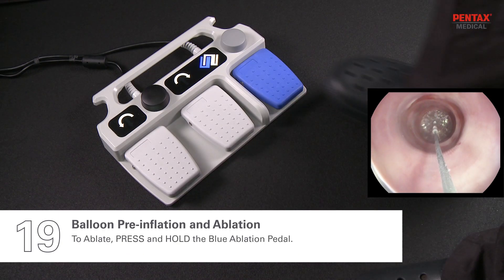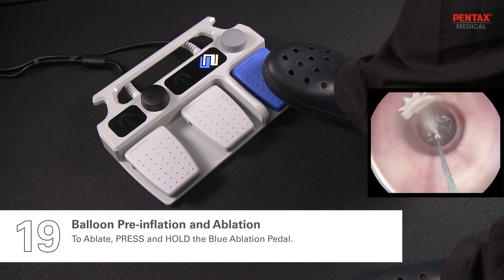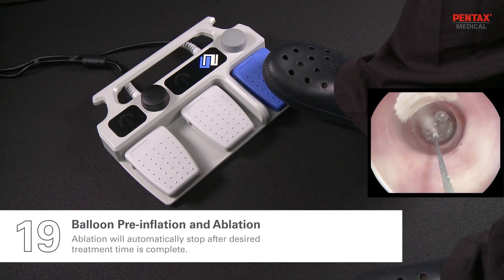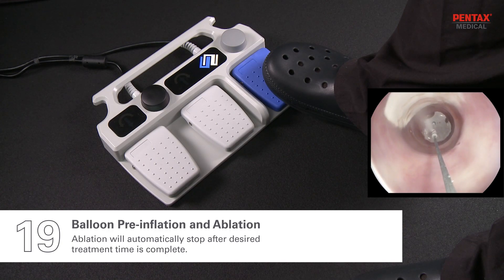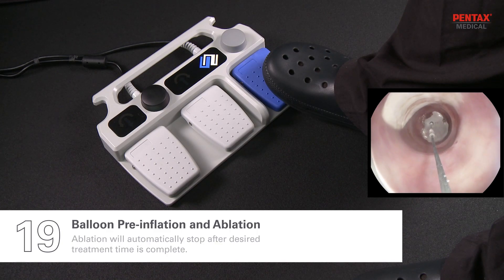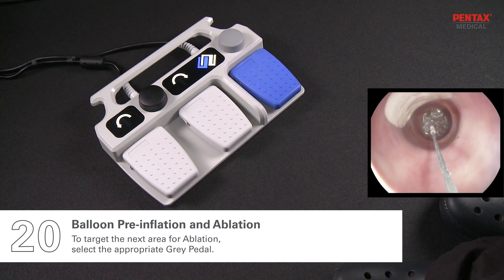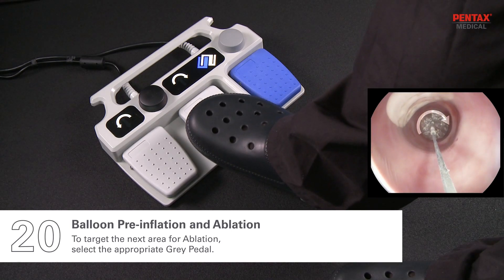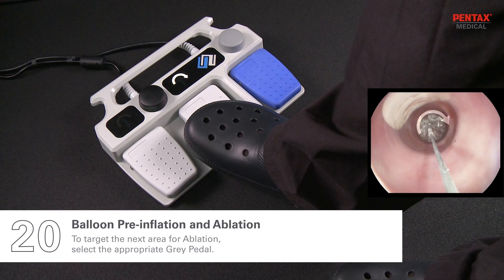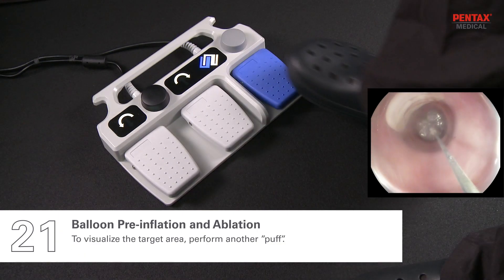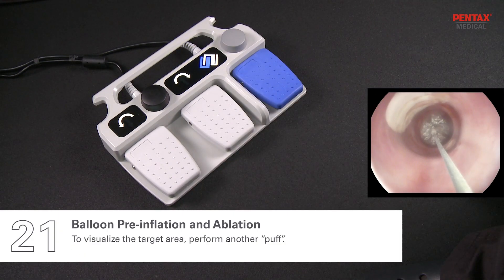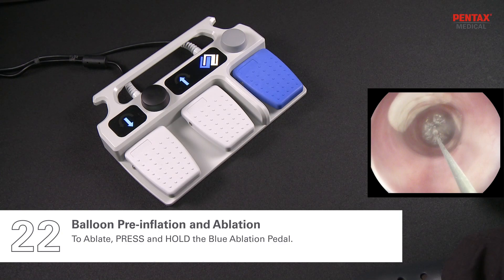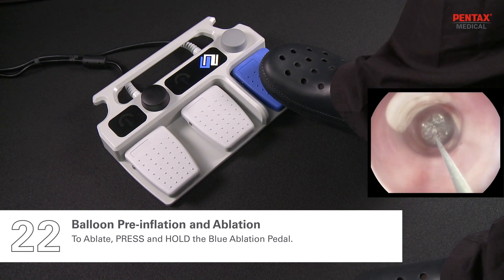To ablate, press and hold the blue ablation pedal. Ablation will automatically stop after the desired treatment time is complete. To target the next area for ablation, select the appropriate gray pedal. To visualize the target area, perform another puff. To ablate, press and hold the blue ablation pedal.